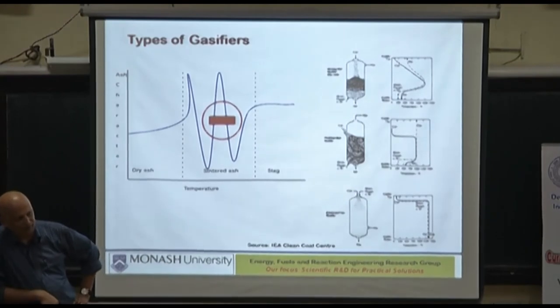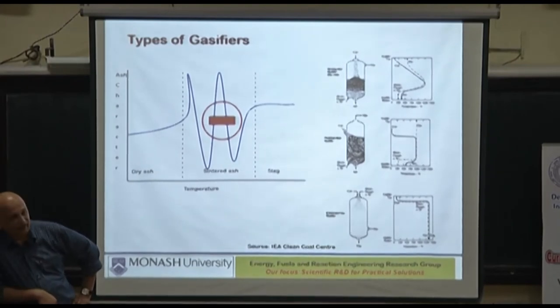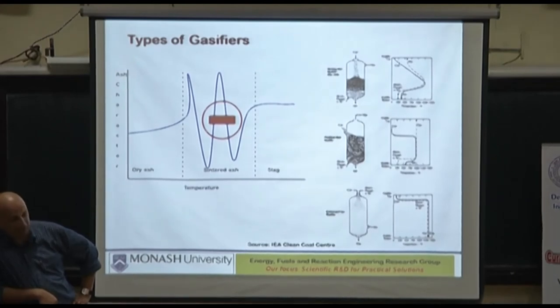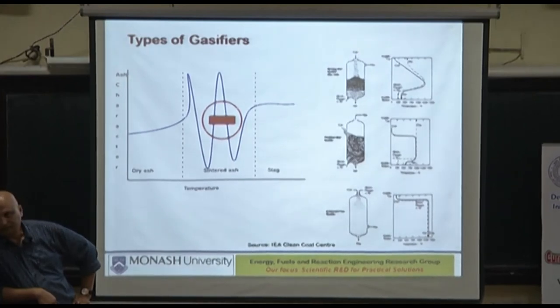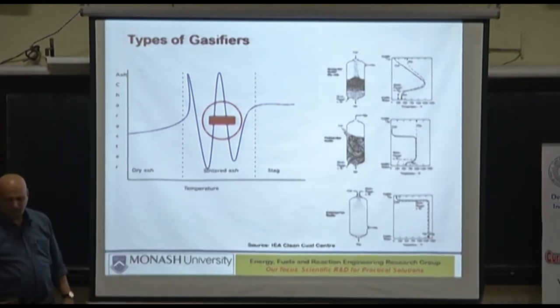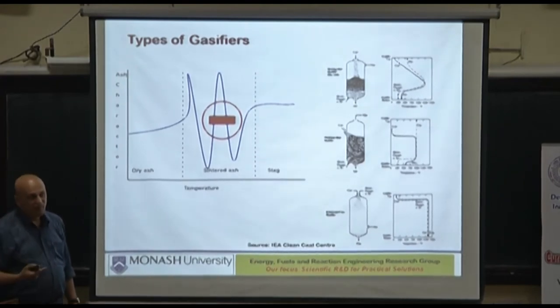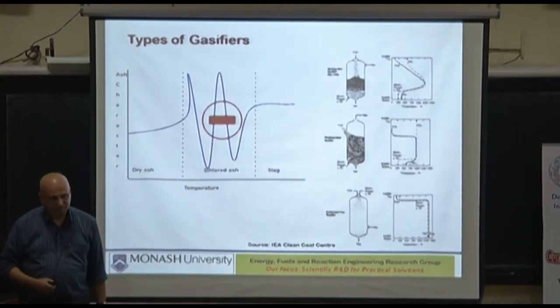Controlling a fluidized bed gasifier at high pressure is a challenge. And it becomes even more of a challenge if your ash has a lot of iron and calcium and sodium in it. If it is only aluminosilicates, not a problem, because you will have to operate it at a high temperature zone. In fact, you will be required to lower its slagging temperature.